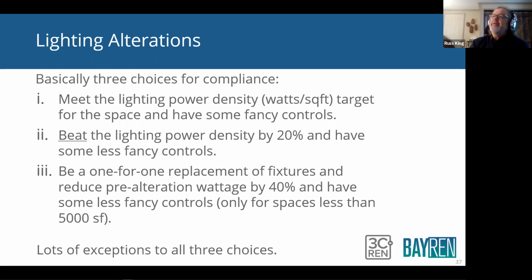So let's say you've got a 2,000 square foot retail space and they want to replace the fixtures, okay? So they come in, they replace all the fixtures from old fluorescent fixtures, you know, the 4-foot tubes, and they want to put in new LED fixtures. Well, LEDs are way more efficient than fluorescent. So if they just replace all those one for one, they will reduce it by 40%. So they're going to be 40% less. They can do that, okay? That's the other type of alteration that is allowed, okay?